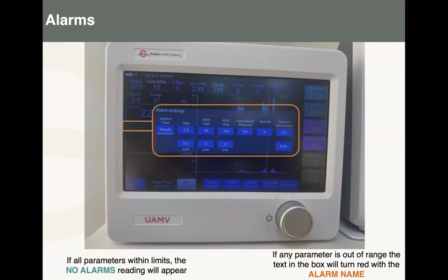You can also set the limits. For example, here you can see the MV, low MV, PIP, low FiO2, all of this. All of this you can change accordingly. Remember, before you start a patient, make sure you review these alarm limits and make sure they are within an acceptable physiological range, to avoid unnecessary alarms. Next.